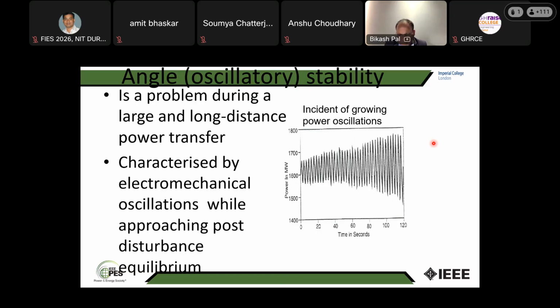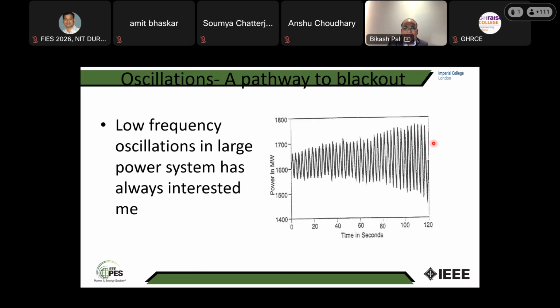So there are 400 kV lines. Typically, you could observe those oscillations if there is an analog power meter. This oscillation is essentially a pathway to blackout. So what is the nature of the oscillation? One can conceptualize that all the power plants that I just named, in Durgapur or Farakka, and then on the other side, Korba and also Rajasthan and Uchahar in Uttar Pradesh. There are many of these. Between them, there is a transmission circuit.